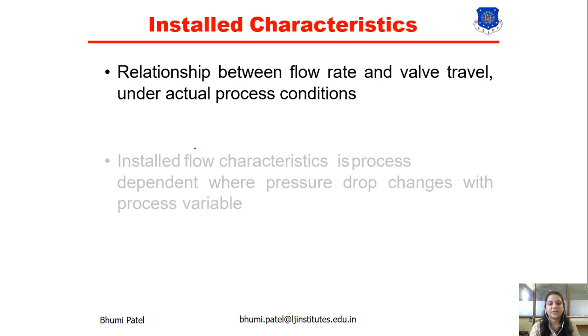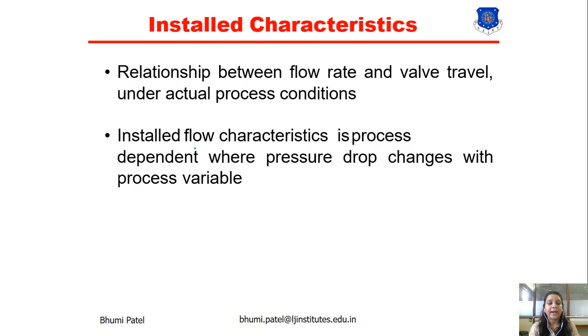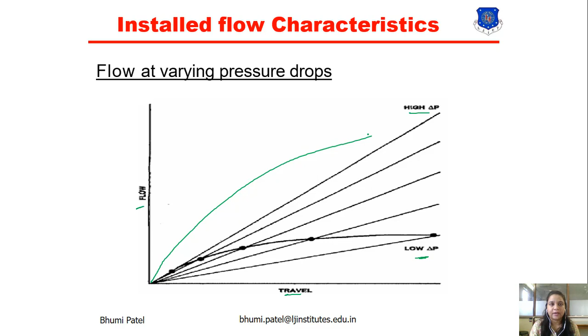Now installed characteristic is the relationship between the flow rate and the valve travel under the actual process condition. So installed flow characteristic is process dependent, where pressure drop changes with the process variable. For the varying pressure drop we can get this type of flow characteristic. Here you can see this is the travel versus flow: at the low differential pressure we can get this type of curve, and for the high differential pressure we can get this type of flow characteristic.